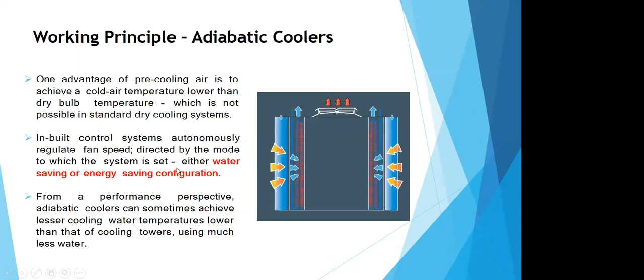So either way, if somebody is interested in having energy saving as their priority, then we can utilize the pre-cooling effect to the maximum and minimize the power consumption by optimizing the fan speeds through a control panel. So from a performance perspective, the adiabatic coolers can achieve lower cooling water temperatures than the cooling towers, while using much lower water consumption.